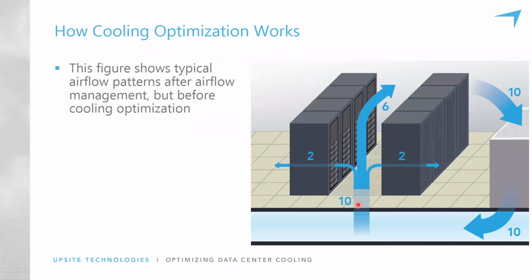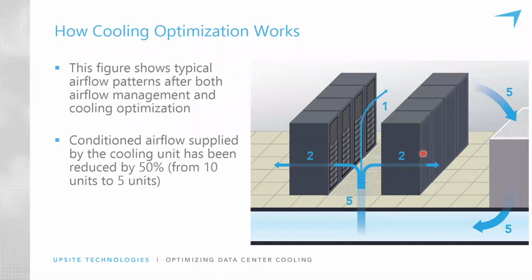Now that we've improved the airflow through the room, we've done all the airflow management methods: blanking panels, sealed the raised floor, put doors on the ends of the aisles and baffles or a roof on top of the cabinets. We now have the ability to reduce fan speeds or turn off half the cooling units in the room and realize those benefits.